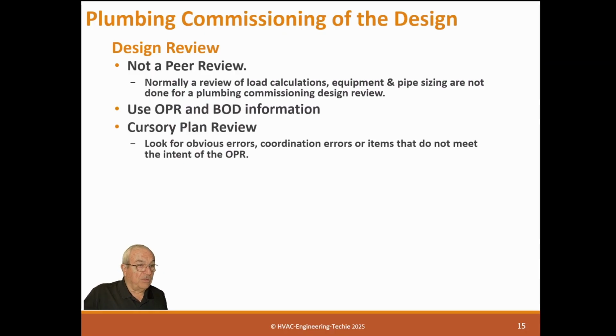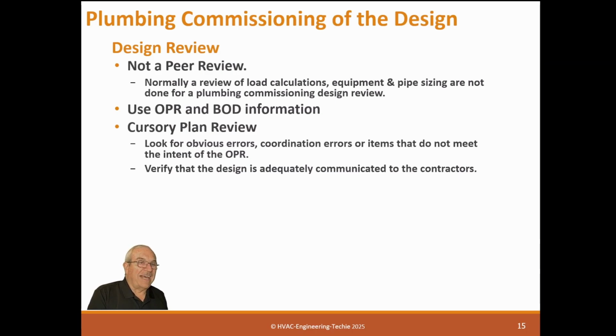You just want to make sure in general it's got simple things. And then every once in a while, if you find an issue that pops up where you actually need to go look at pipe size, then you might do that. I've seen it several times on water where it makes no sense, where a 4-inch main feeds 3 other 4-inch mains, and you go, wait a minute, this doesn't feel right to me. And you've got to check that out to make sure that the pipe sizing is done correctly. Verify that the design is adequately communicated to the contractors. You know, I have this old saying, and I've said it many times before: if you show a system exactly perfect on the drawings, this is exactly how it should be, you have a 50-50 chance of actually getting it installed that way.